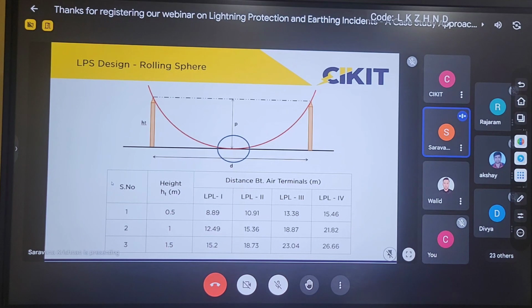If the same layout is provided to different designers who are performing this risk assessment and design calculations, the output won't be the same, because based upon the position and the height of the air terminals used for the calculation, the number of air terminals will be different. So even though the building dimensions are the same, if different people perform the design, the number of air terminals and parameters like the height of the air terminals won't be the same.